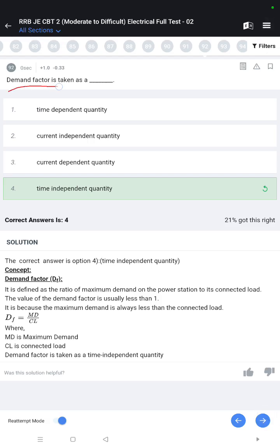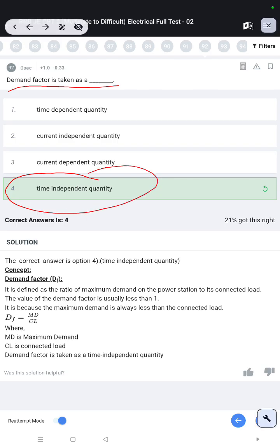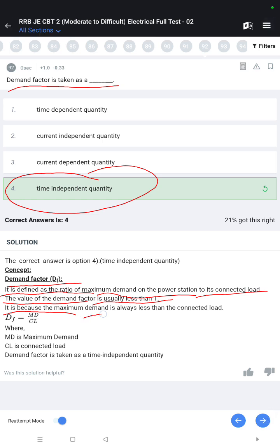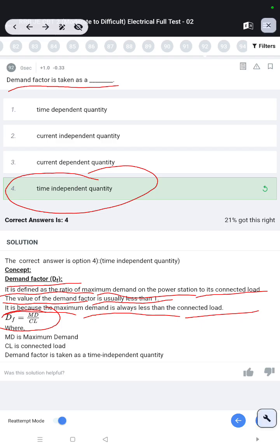Demand factor is taken as a time independent quantity. Demand factor DF is defined as the ratio of maximum demand on the power station to its connected load. The value of the demand factor is usually less than 1. It is because the maximum demand is always less than the connected load. DF = MD / CL. The trick to remember is DMD CL, where D is demand factor, MD maximum demand, CL connected load. Demand factor is taken as a time independent quantity.